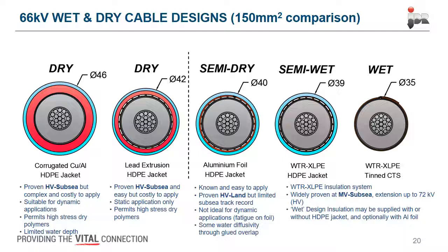What we wanted to do was to ensure that we had a solution that could work in a lower cost environment for offshore floating wind. And so that's one reason why we preferred a semi-wet design. So there's no metallic barrier to keep the insulation system dry. You've still got an outer PE sheath to provide mechanical protection, and it will also inhibit water ingress, but we would happily allow the insulation system to get wet. That's in contrast to a semi-dry design where an aluminium foil layer is used. And one of the problems in a dynamic application is that the fatigue is always an issue around the outside of the cable. And having a thin foil layer, in our view, would not be adequate for a dynamic application.